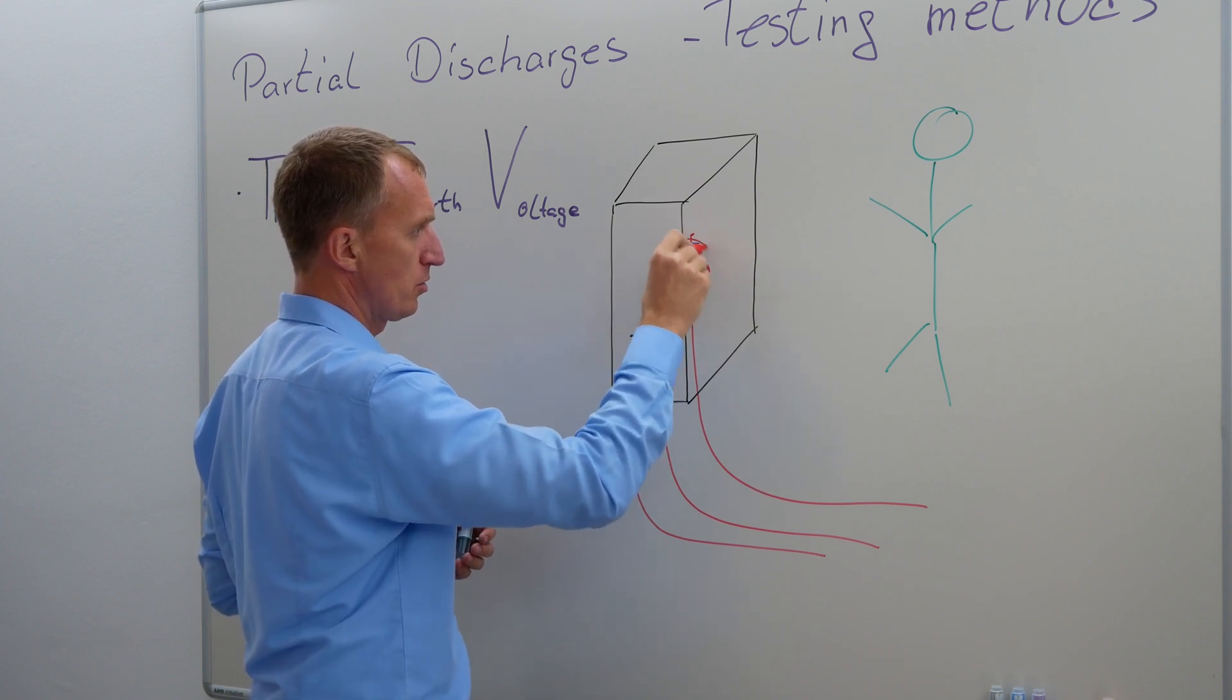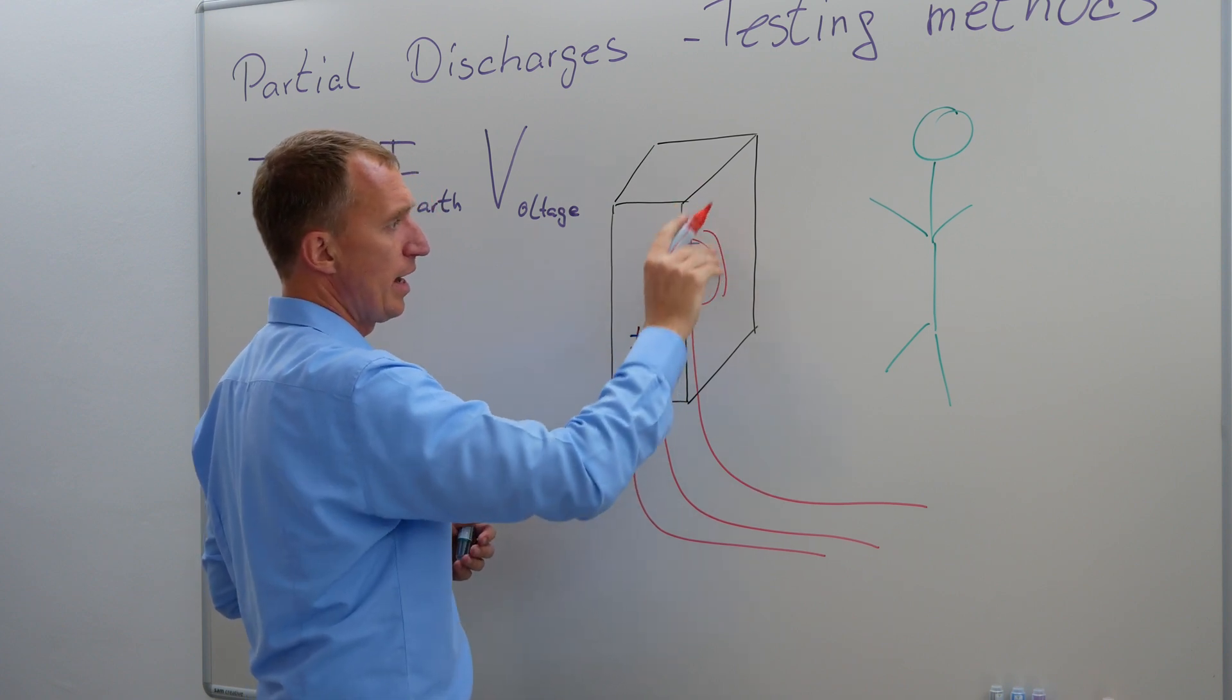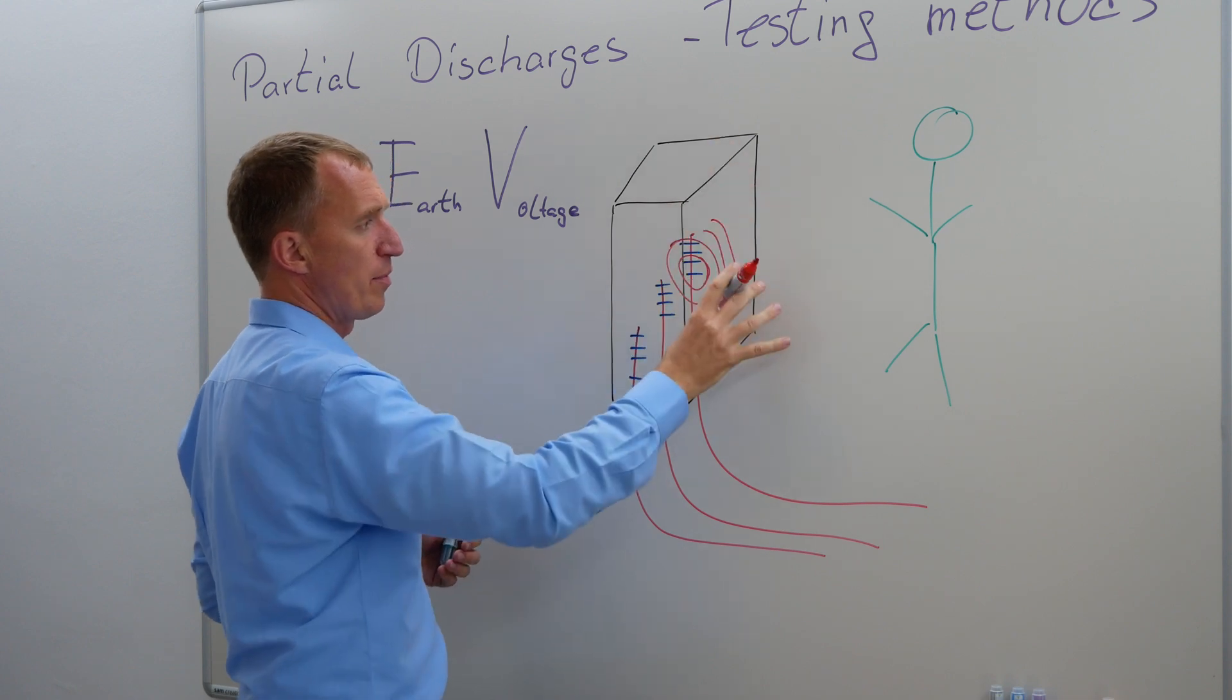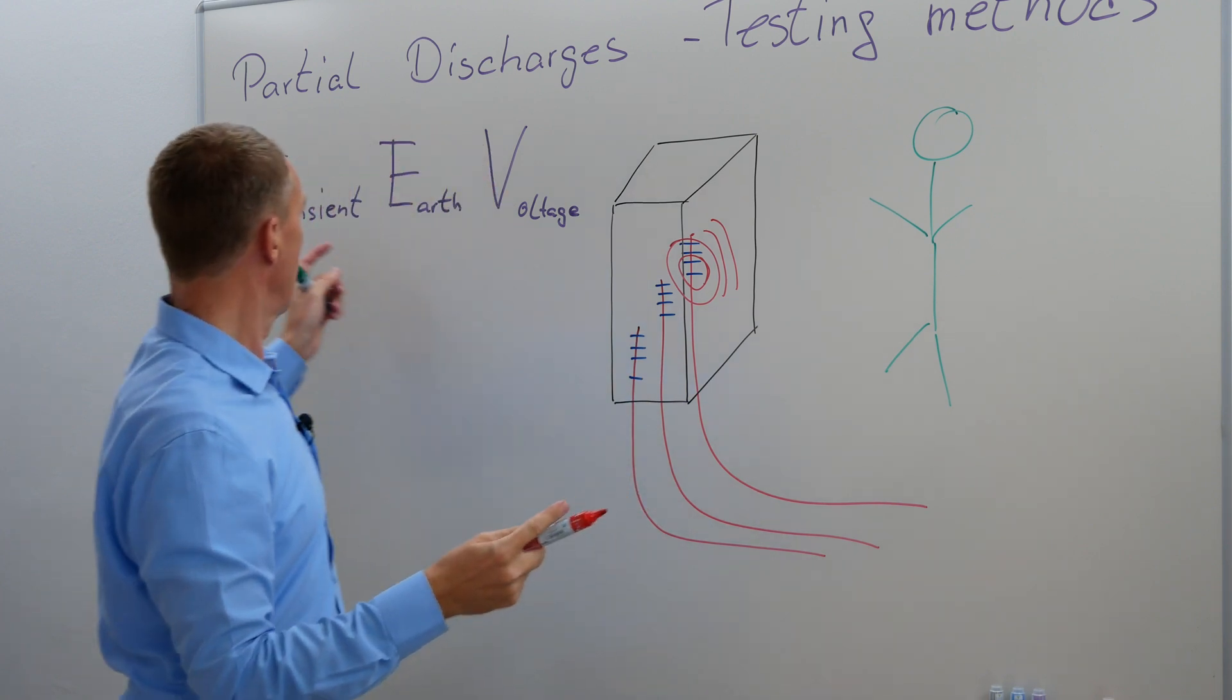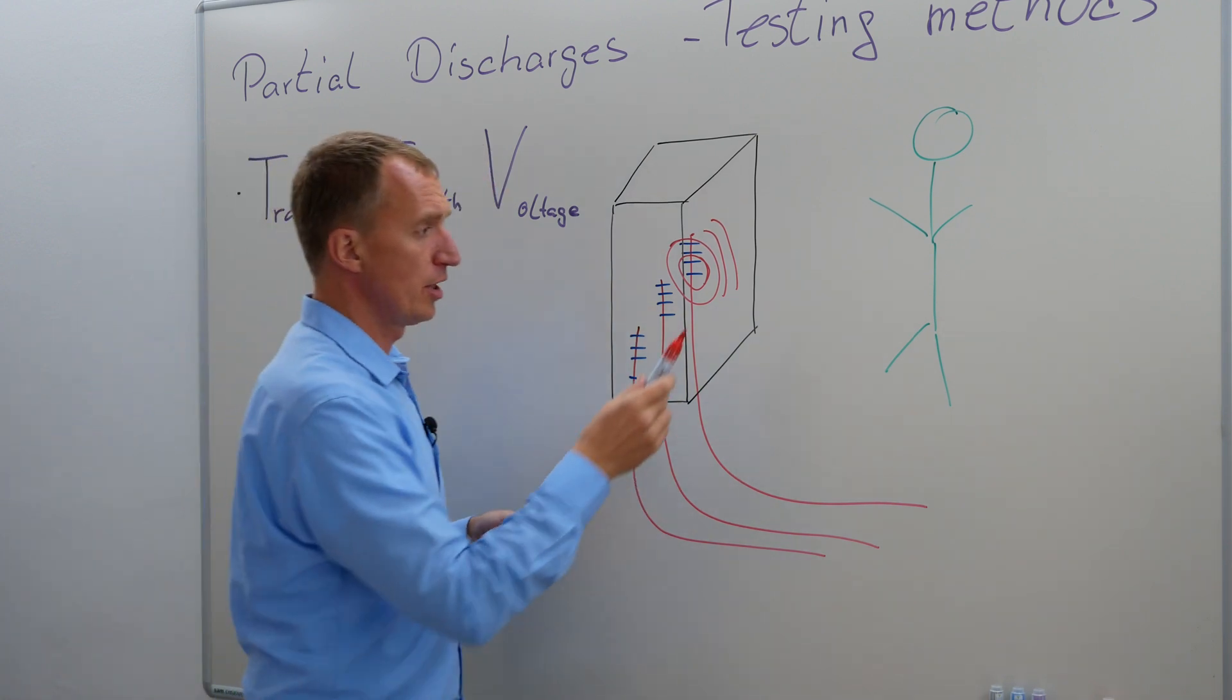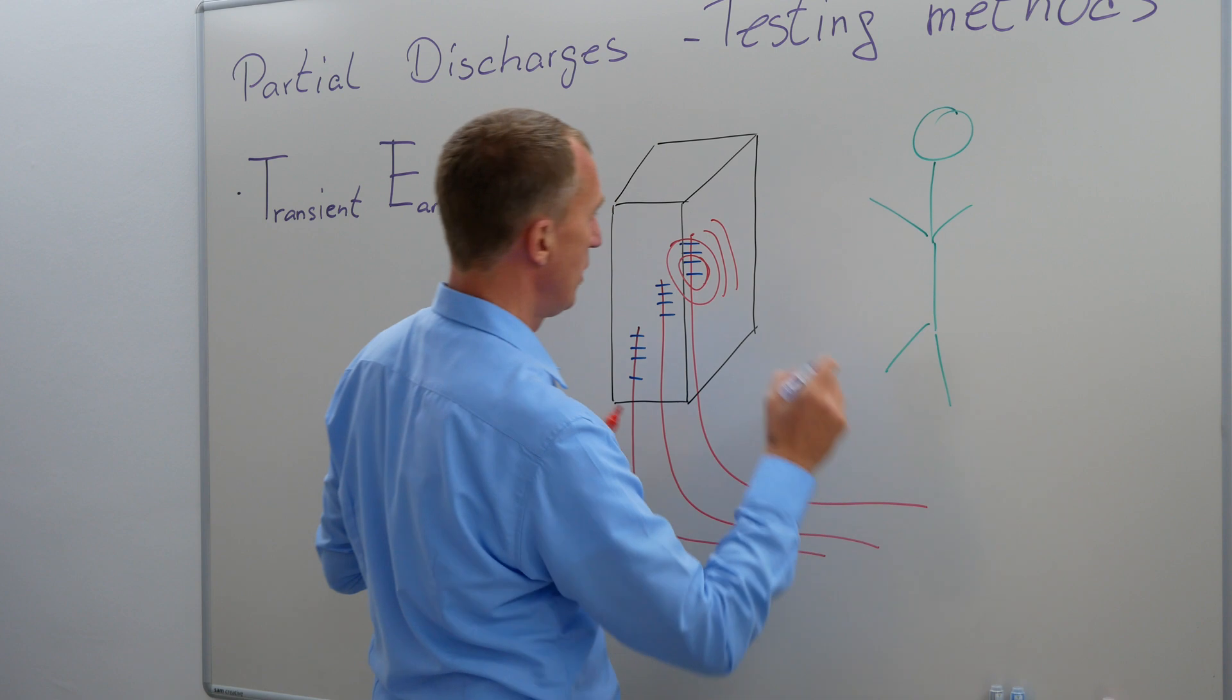Actually, this is round, right? But I'm only caring about this part. Now it hits my metal casing and I will have a small spike, a transient earth voltage, which I could pick up if I have a sensor here. So I could place a sensor here.